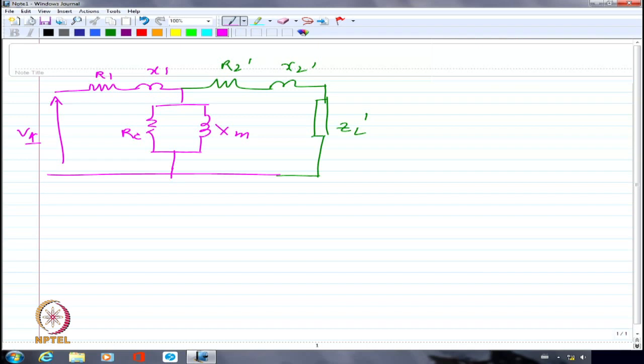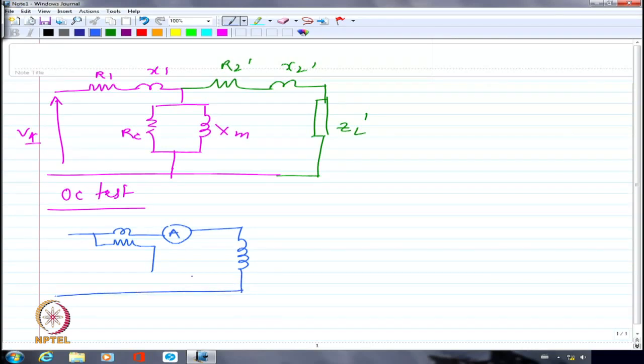In this case, we initially talked about the OC test. In the OC test, what we said was that we are going to have the transformer connected through a wattmeter and an ammeter. This is applying the voltage to the winding, which will be the low voltage winding. We are going to call this the LV winding, whereas the winding which is open circuited is going to be the HV winding. Right? So now we will also measure the voltage applied here. We are going to call this voltage V1, whatever is applied.